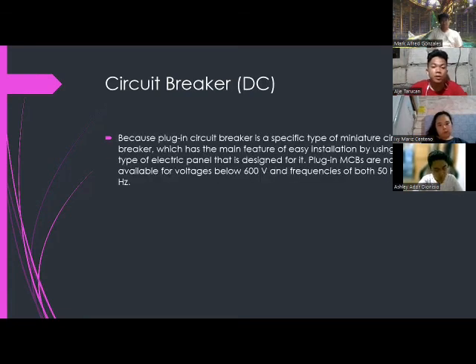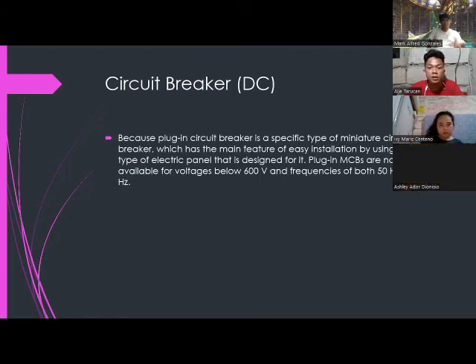Is the circuit breaker DC. Yun nga, iwan tayo kung ano, kung yung MCB ba or yung plug-in circuit breaker or sa direct DC circuit breaker. Kung yung plug-in ba o yung MCB type. Ang napili ko ay yung plug-in circuit breakers because it is a specified type of miniature circuit breaker which has the main feature of easy installation by using a special type of electric panels that is designed for it. Plug-in MCBs are normally available for voltage below 600 volts and frequency of both 50 Hz and 60 Hz.